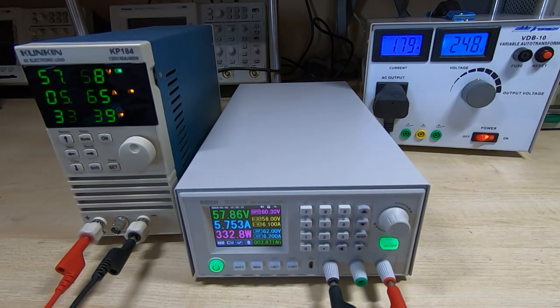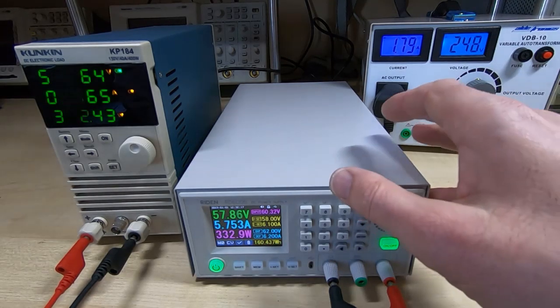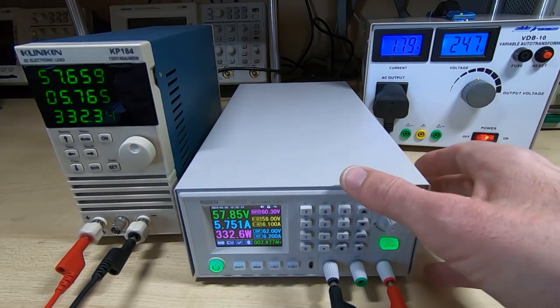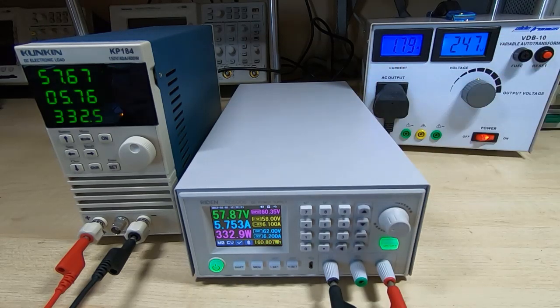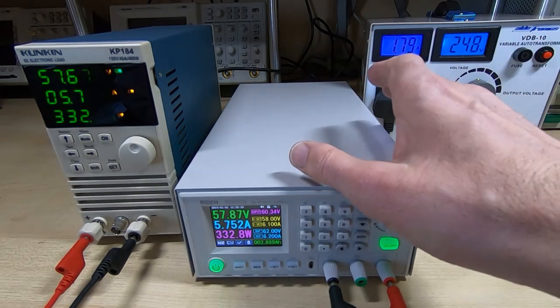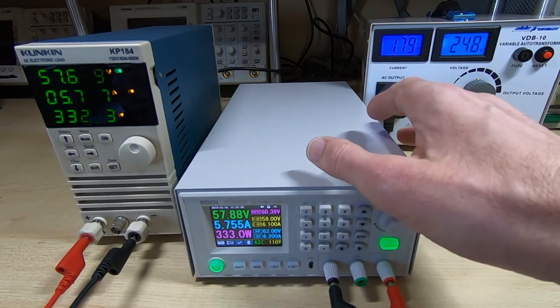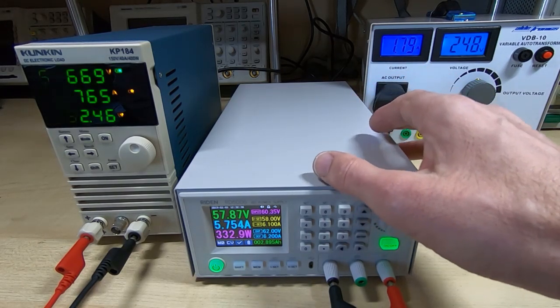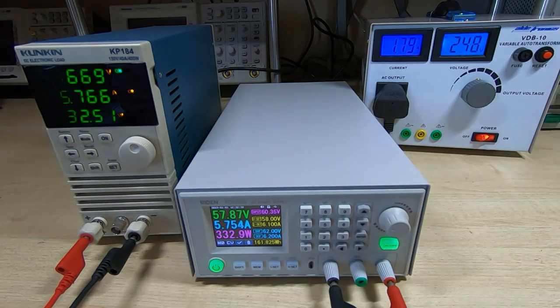So that's something to bear in mind if you're designing something and you're checking the thermal performance and you want to attach probes and sensors to monitor temperatures. Make sure you do it with all the covers in place. It doesn't follow necessarily that removing the covers will make it run cooler. Removing the covers can make certain parts run hotter, so that's just something to bear in mind. The reverse is true, of course, you could end up with a hotter enclosure if it's not properly thermally managed.